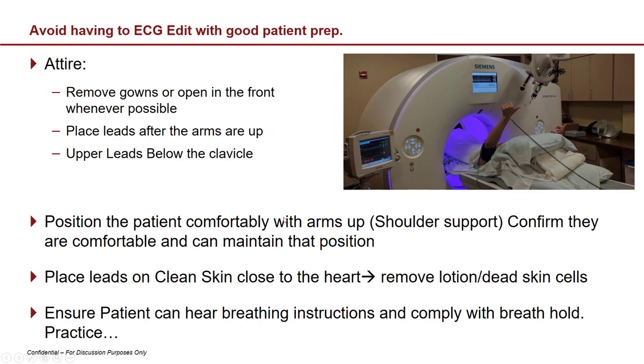Use the GOIF acronym — Gown Open In Front — so you can place leads comfortably without the gown pulling leads and removing contact. Always have arms up before putting leads on, though some patients can't because of shoulder pain. Keep leads generally below the clavicle; if arms are down when placed and you raise them, leads may end up above the clavicle. Patients need good shoulder support and must not move arms during the cardiac scan, since muscular movement also causes electrical signals. Place leads as close to the heart as possible and remove lotion and dead skin cells with alcohol.